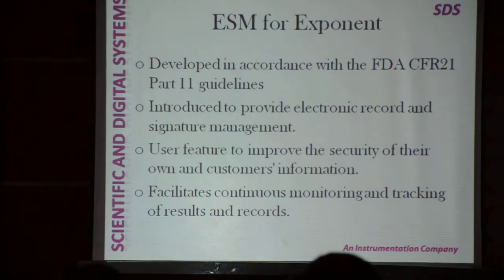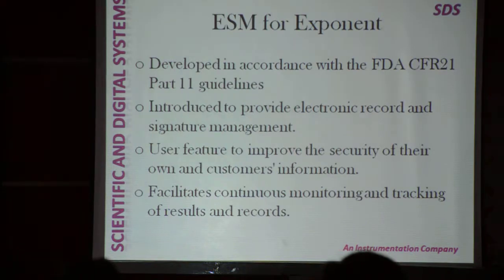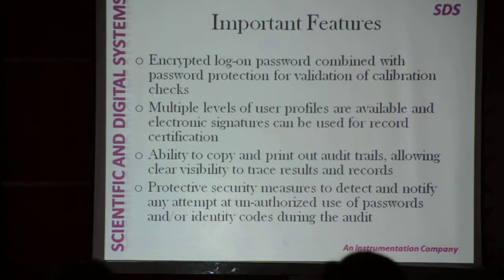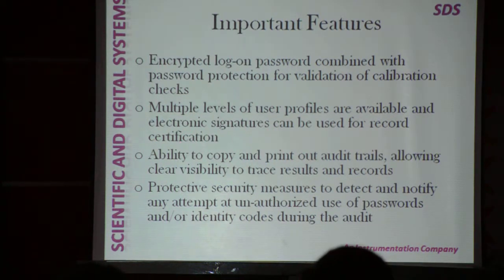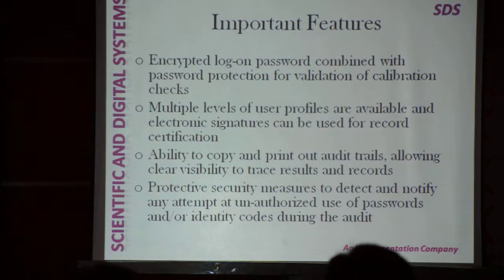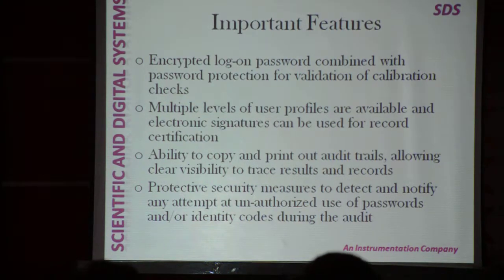The ESM module is an attachment to Exponent software — it's a very useful add-on. Some important features: it has a logon password and you need to validate it periodically as 21 CFR requires. You can create multiple levels of user profiles, which are available with reporting, reports, and signatures. It can copy and print out all the information, and you can print out audit trails, which will make visible results and records available for a long time.